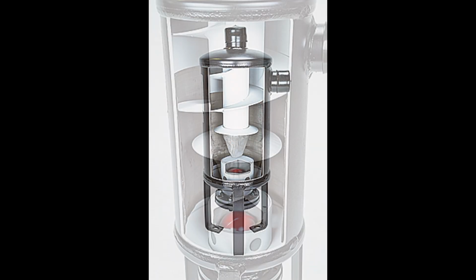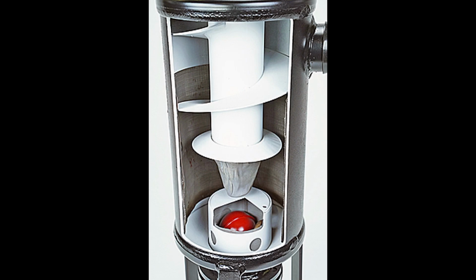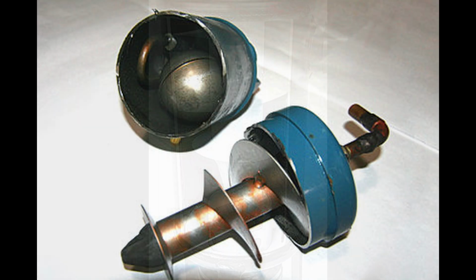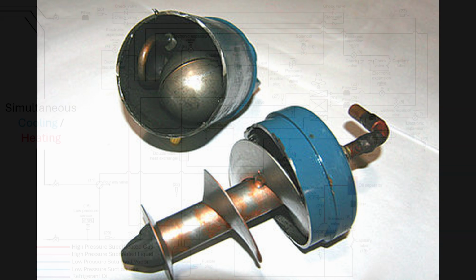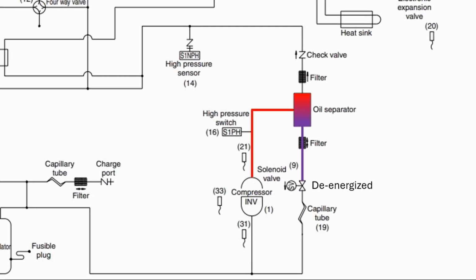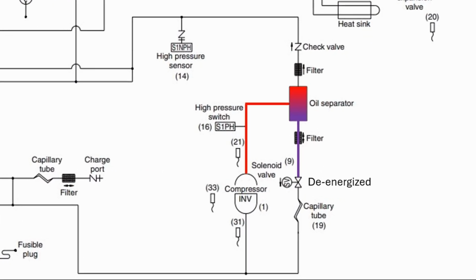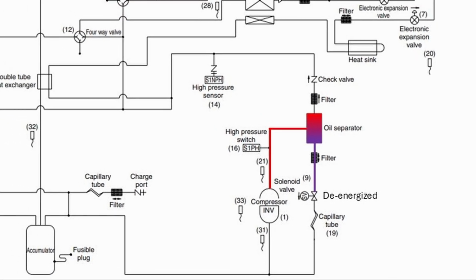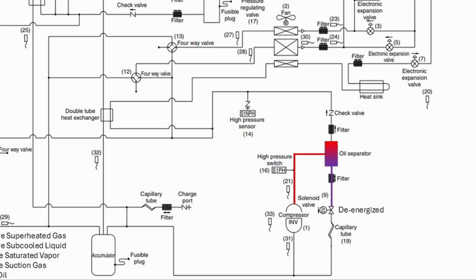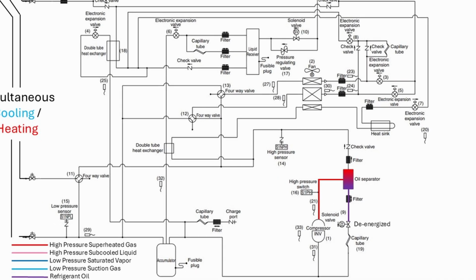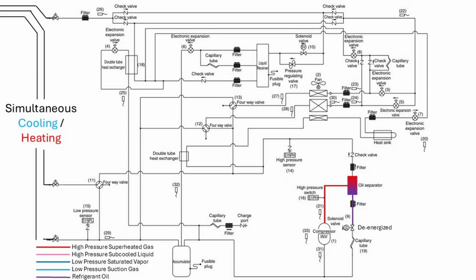The oil separator is a spiral device that uses centrifugal force to remove oil from the refrigerant. The oil leaves the oil separator and passes through a solenoid valve on its way to the compressor. The solenoid valve is activated by the main control board when the system goes into an oil recovery mode. Oil recovery mode is activated when the compressor runs at low frequencies for a specific amount of time. It's at lower compressor frequencies where the oil separator is the least effective.